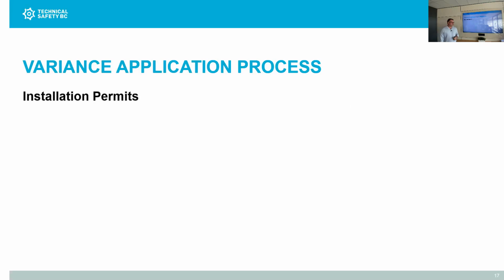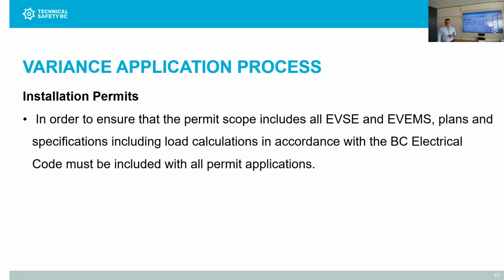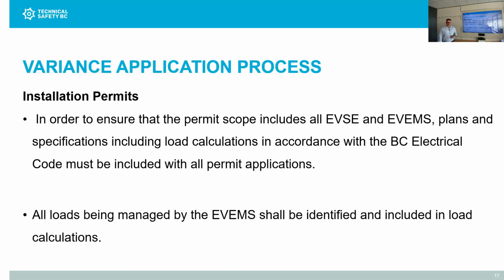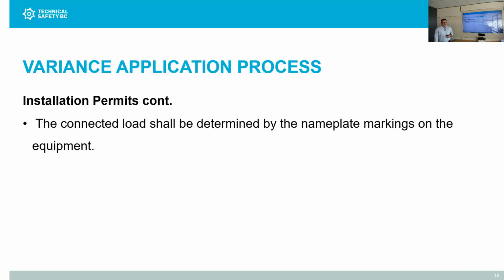So if we're going to be needing the variance and we're going to be inquiring about an installation permit, we're going to need to ensure that the permit scope includes all EVSE and EVMS plans and specifications, including load calculations in accordance with the BC Electrical Code, and those must be included with all permit applications. All loads being managed by the EVMS need to be identified and included in your load calculation. The connected load shall be determined by the nameplate marking on the equipment.